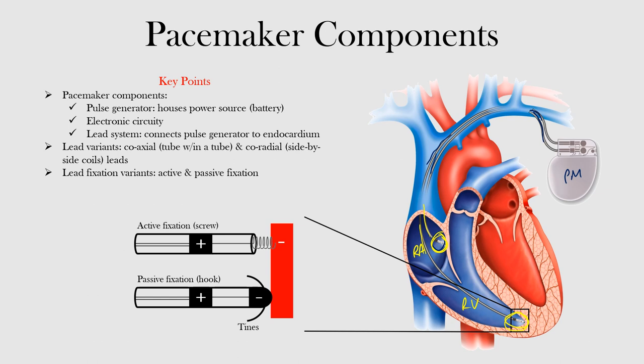If active, the cathode has an electrically active tip that is inserted into the myocardium for mechanical stability. If passive, the cathode is not inserted into the myocardium. Instead, electrically inert tines anchor the leads.